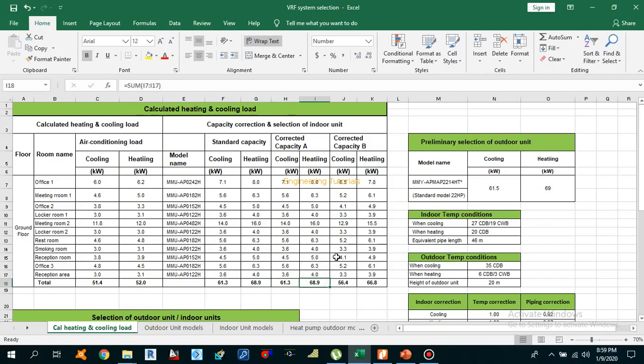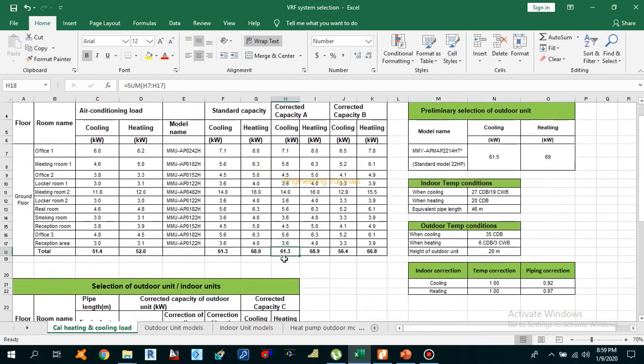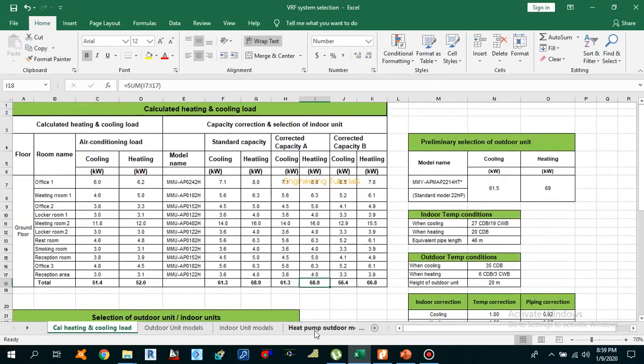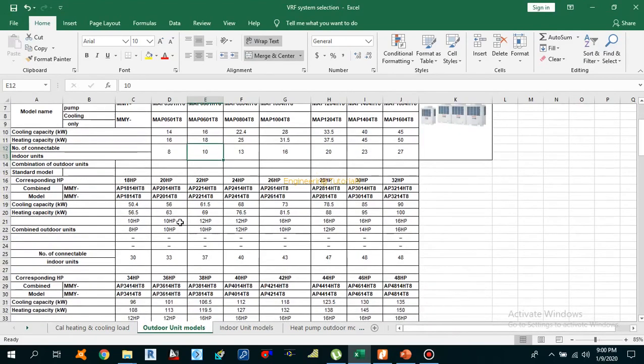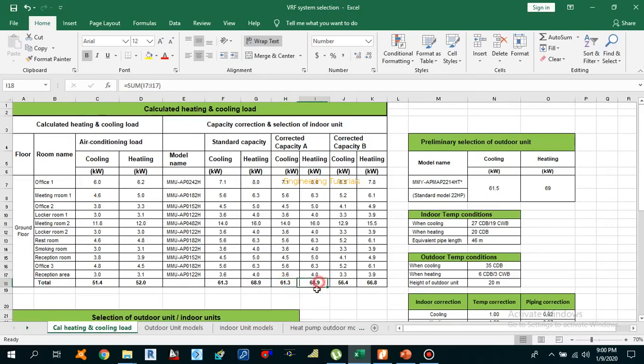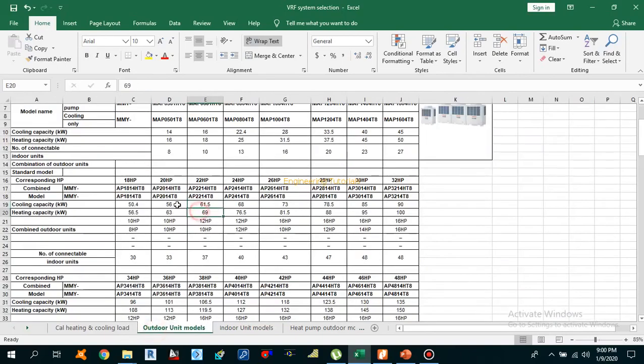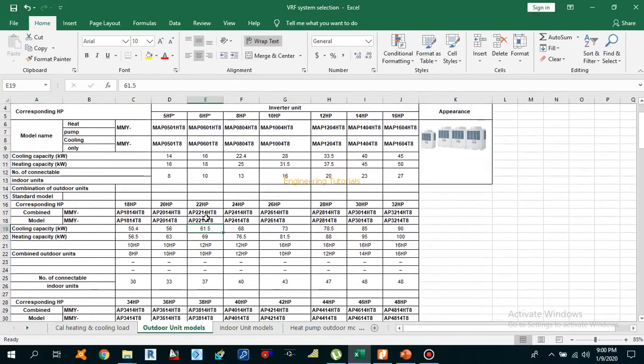At the same time, we have to check both connectable indoor unit numbers and outdoor unit diversity. So we are going to select this outdoor unit based on this corrected capacity sum for cooling and heating. So let's say we have calculated 61.3 kilowatt for cooling and 68.9 kilowatt for heating. So move to our outdoor unit models over here. How much have we calculated here? 61.3 and 68.9.